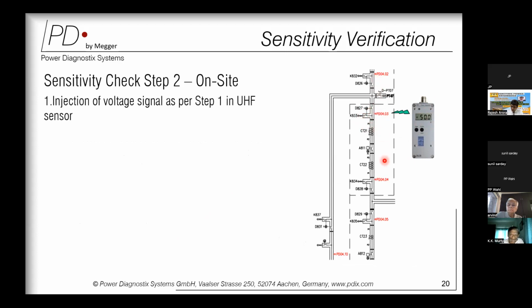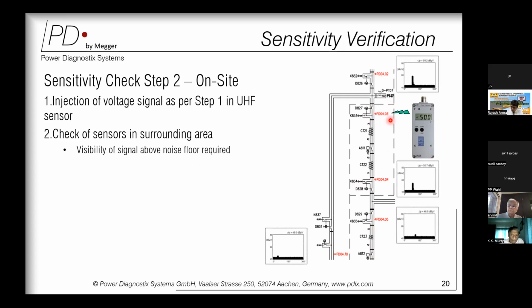As we see from this GIS SLD, there are six sensors in a particular bay. We will inject a pulse into one particular sensor, and we will check the sensors in the surrounding area. That means we connect the measuring instrument to the surrounding sensors, and the qualification requires that all these nearby sensors should read the signal, at least some part of the signal, above the noise floor.